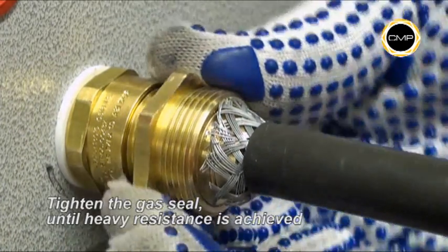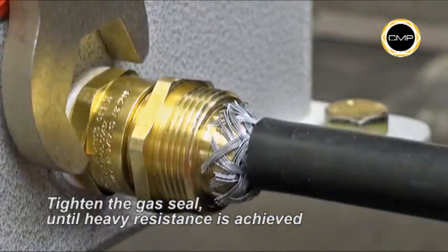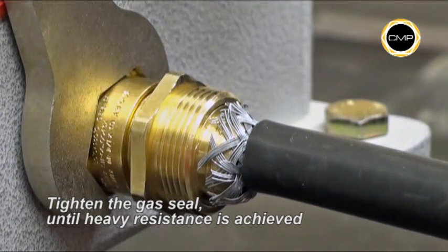Whilst pushing the cable gently forward to maintain contact between the armor and the armor cone, hand tighten the gas seal until a heavy resistance is achieved, then tighten a further full turn with a spanner.